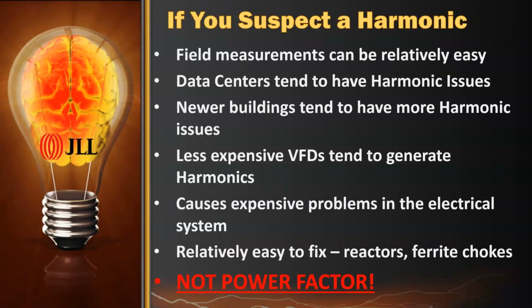So the field measurements are pretty easy. We're going to talk about that in a minute. I can tell you that data centers usually have harmonic issues. Newer buildings do too. Less expensive VFDs, talked about that before, will generate a harmonic, and it can cause issues in the system.